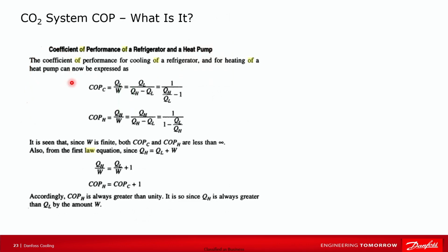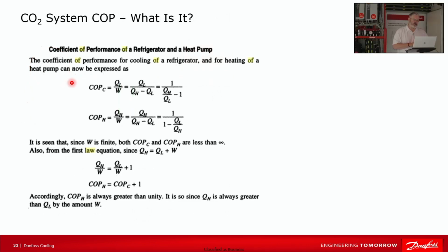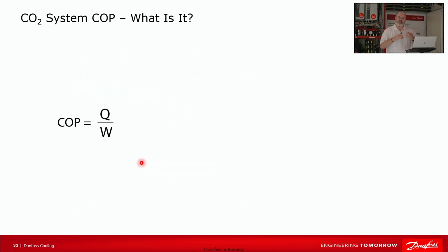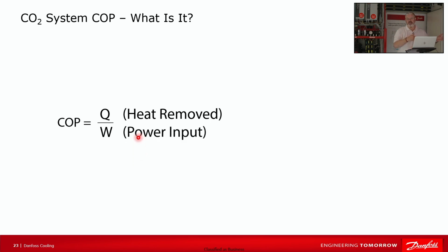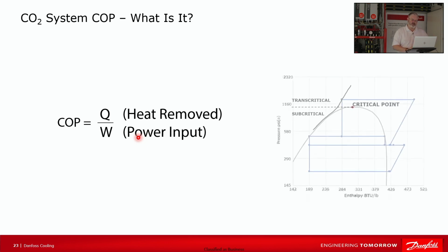So I mentioned COP. You'll hear this thrown around a lot when people talk about CO₂. It stands for coefficient of performance. And we're going to spend the next hour going through this formula step by step until everyone has it memorized. I'm kidding. The simple version of COP means work over energy input into the system. For us, Q equals the amount of heat removed. The work we're accomplishing is taking heat out of our display case and rejecting it into the ambient air, and to do that we have to put in a certain amount of wattage. So the short definition of COP is heat removed divided by the power input into the system.